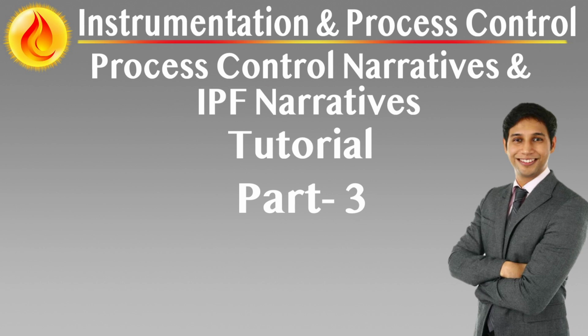Types of cause and effect diagrams. Two distinct types of CEDs are typically generated. Design CEDs, developed by the engineering contractor during the project lifecycle. These diagrams reflect the protection logic as defined during the detailed design phase. They are issued alongside IPF narratives and become part of the formal review, comment, and approval process. Design CEDs are eventually updated to as-built status following commissioning.